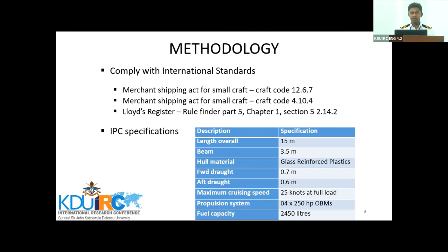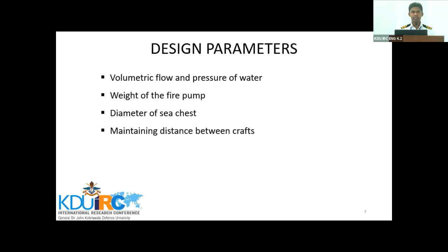Design parameters: an exact location was identified to have the sea chest without obstructing the stream water flow for the hull. The following design parameters were considered to maintain a minimum distance of 20 meters between two craft and to throw the water column with the required volumetric flow and pressure. A system head curve was plotted considering the pump head and flow rate, and pump selection was done by matching the pump head curve with the system head curve.